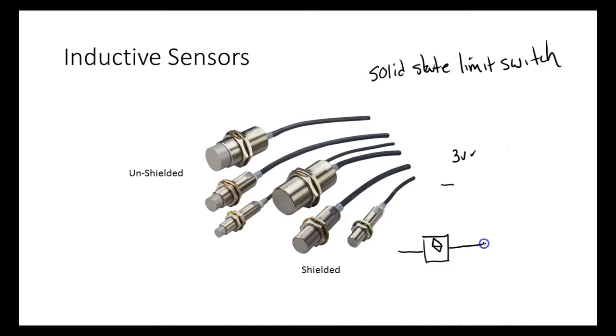Then what they'll do is come over here, and if this right here is a relay coil, there's no power going to it because it literally powers up through the load. So when whatever comes over — I might have a contact over here — as soon as this closes, this guy here is going to drop about 2 volts, and if I've got 24 volts, that still leaves 22 volts to operate the coil, which is still plenty, right?